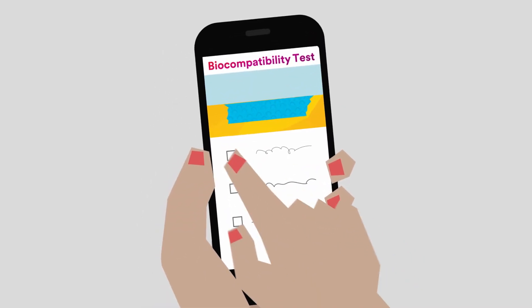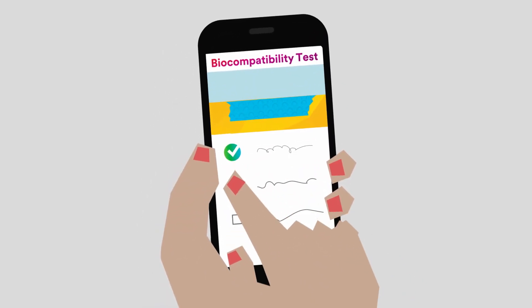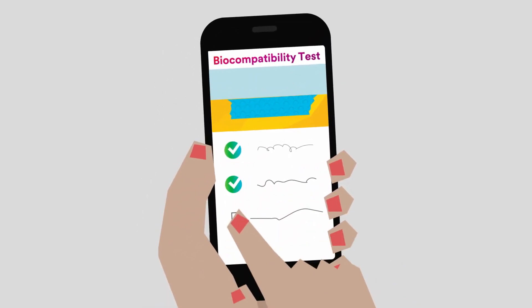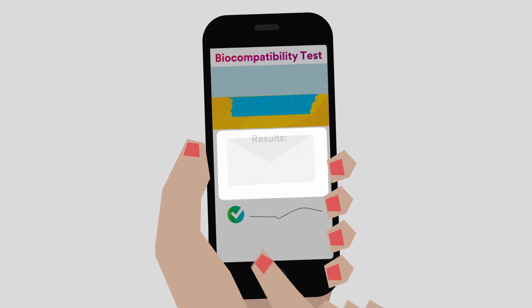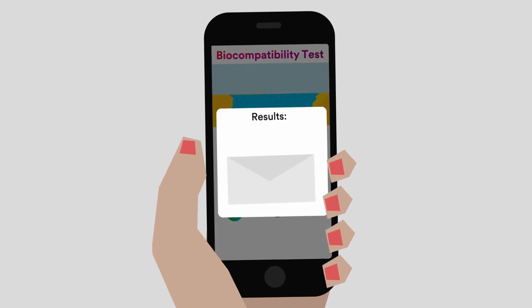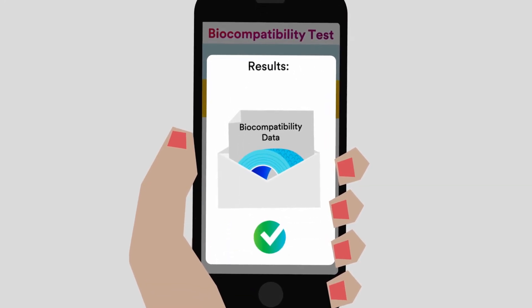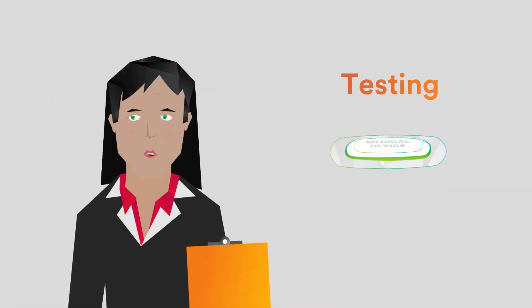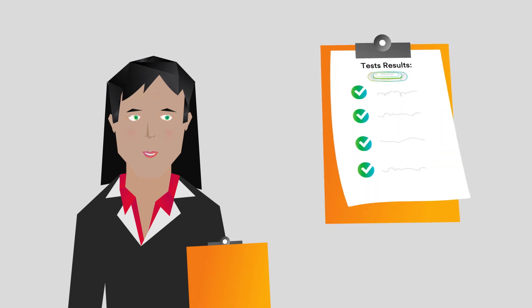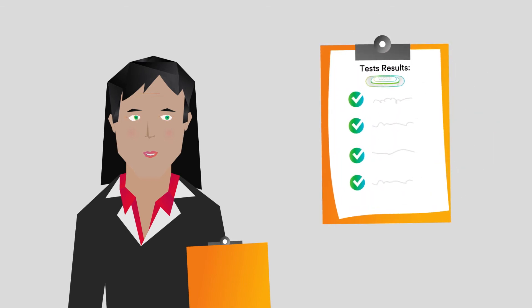Biocompatibility is also an important consideration since it will be worn on skin. 3M can supply biocompatibility summaries for its adhesives, but device manufacturers need to test to ensure that their final device is biocompatible.